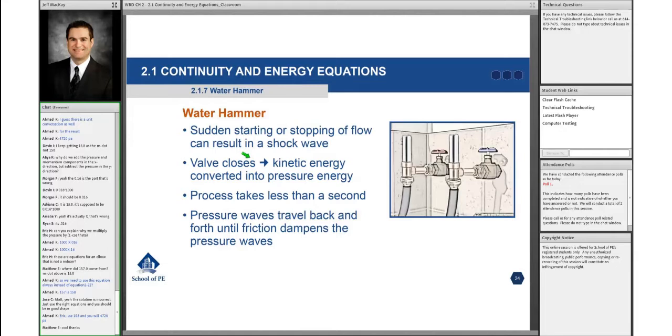It doesn't suddenly dissipate into thin air - it's suddenly converted into pressure energy and it sends a shock wave back through the system. The process is really quick. What happens is that shock wave gets sent back to the source, from the valve back to the source and then back to the valve, back to the source. It goes back and forth until the friction losses in the pipe dampen those pressure waves.